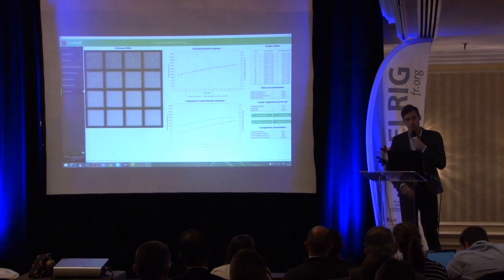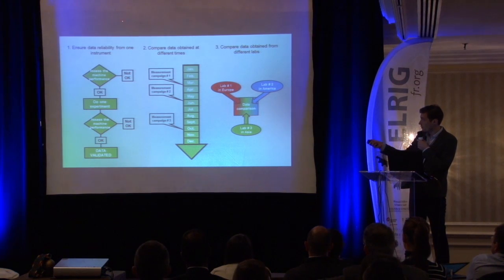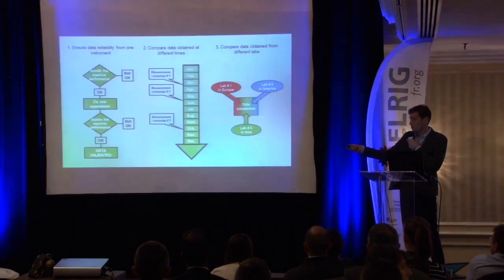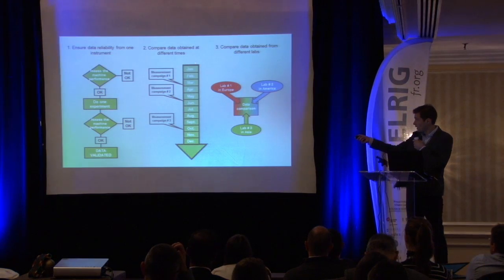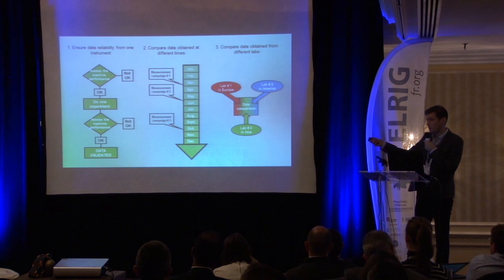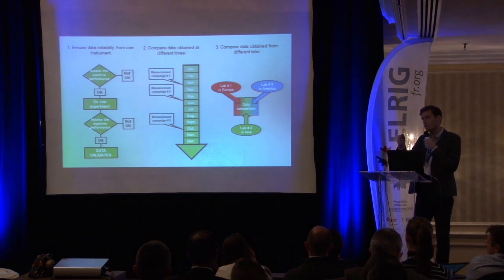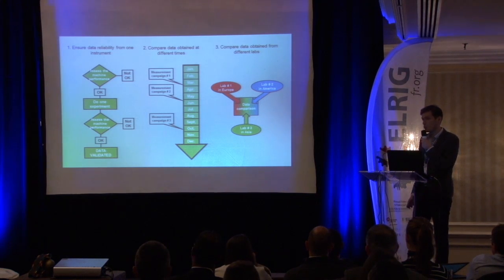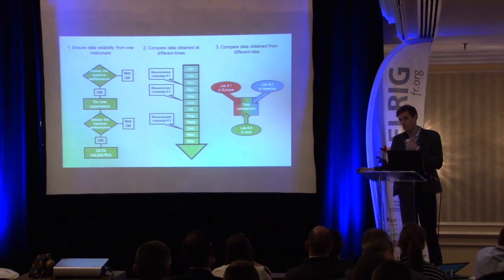Because the slide is stable, you can perform this test before and after a measurement campaign, or daily as routine QC. You can click 'compare response' and the software compares your current response to a stored baseline, revealing any intensity fluctuations. This ensures data produced today is comparable to data from a year before. Each hardware piece is warranted for three years, enabling long-term comparability. You can also compare data across labs in different locations — for example, ensuring data produced in France and China are comparable.